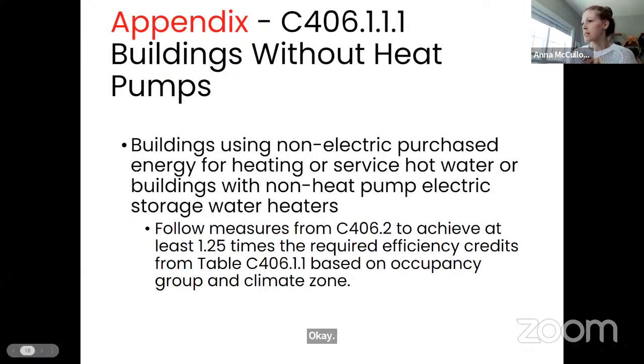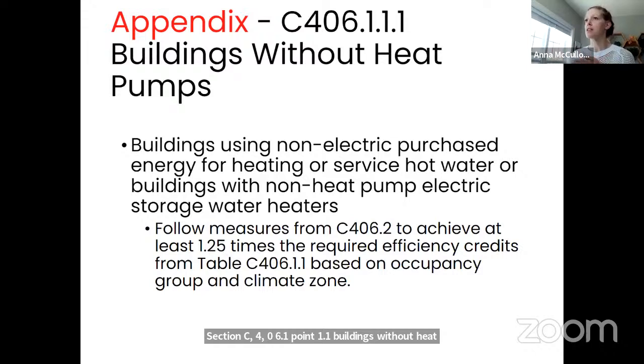Section C406.1.1.1, buildings without heat pumps. This has been moved to an appendix as well. So any building using non-electric purchased energy for heating or service hot water, or any buildings with non-heat pump electric storage water heaters, would be required to achieve at least 1.25 times the number of efficiency credits listed in section C406. So this appendix essentially penalizes projects that are not using heat pumps for heating into providing additional energy efficiency in their designs.